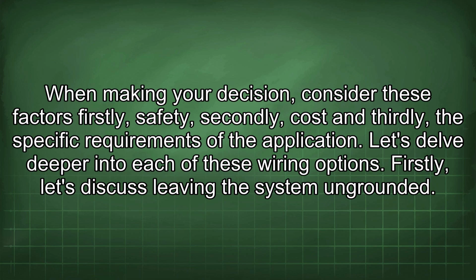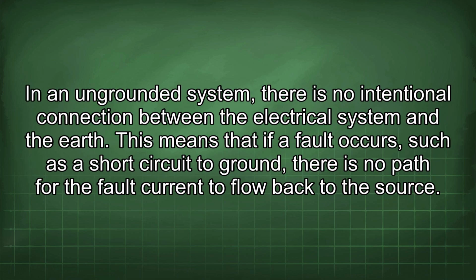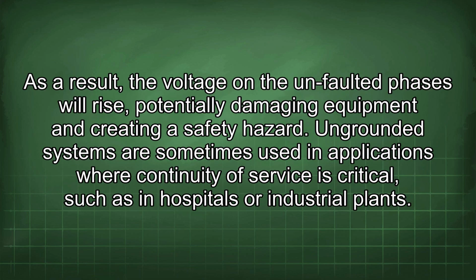Let's delve deeper into each of these wiring options. Firstly, let's discuss leaving the system ungrounded. In an ungrounded system, there is no intentional connection between the electrical system and the earth. This means that if a fault occurs, such as a short circuit to ground, there is no path for the fault current to flow back to the source. As a result, the voltage on the unfaulted phases will rise, potentially damaging equipment and creating a safety hazard.